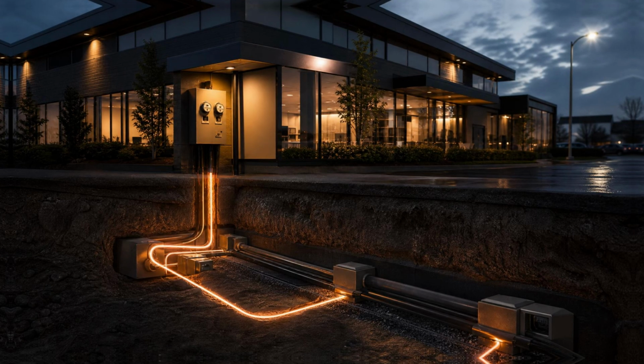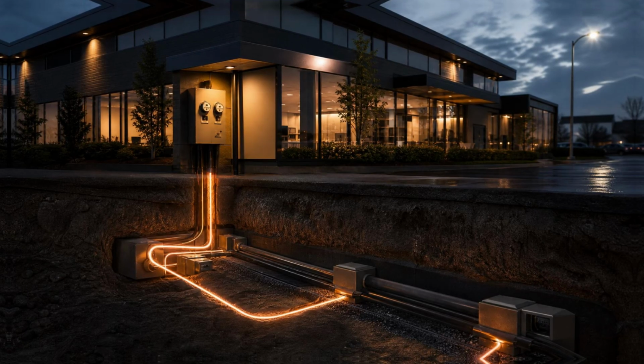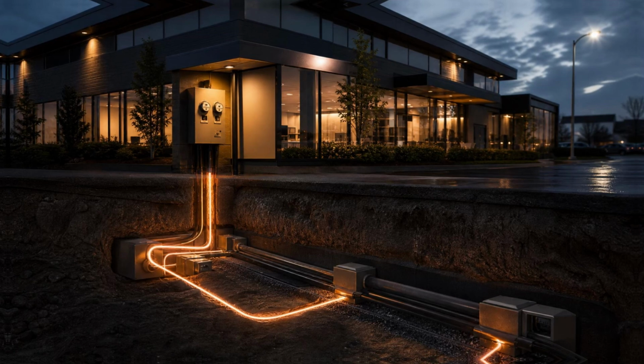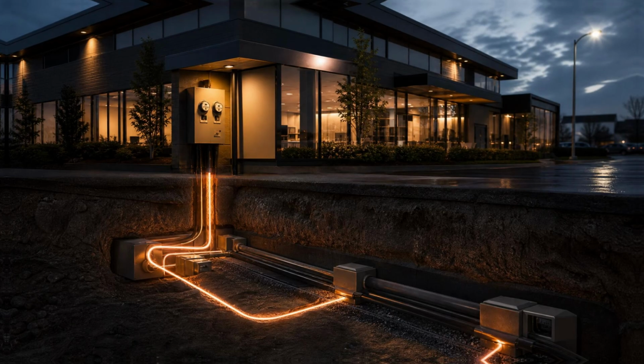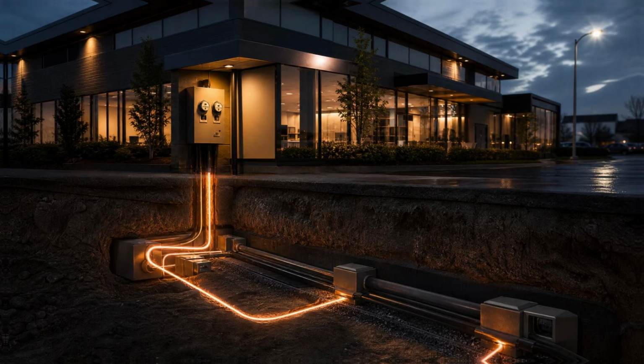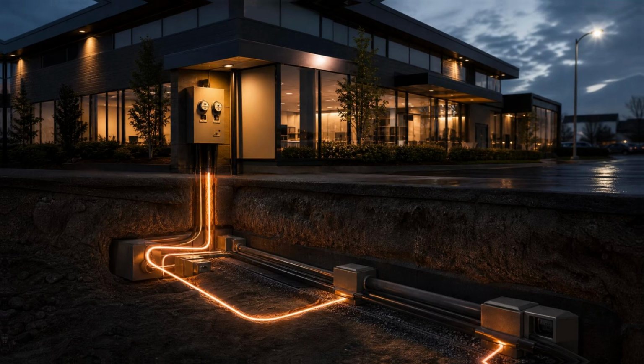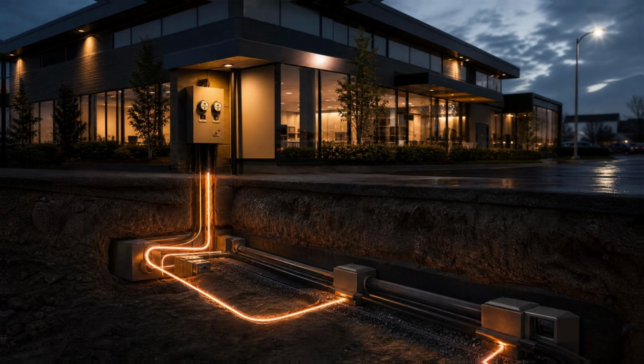Frequency is another characteristic being observed. In North America, utility power is delivered as alternating current at 60 cycles per second, 60 Hertz. That frequency is remarkably stable under normal conditions, maintained carefully by the utility company. But when a power grid is under stress, when generation and load fall out of balance, frequency can shift, and a monitoring system that is paying close attention will see that shift long before most equipment begins to complain.